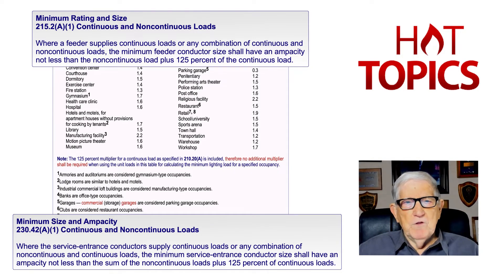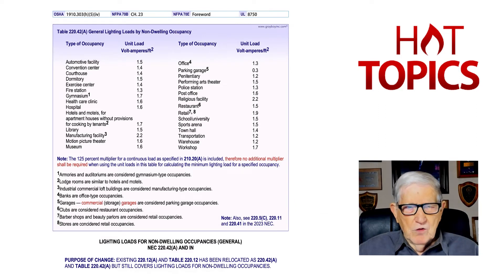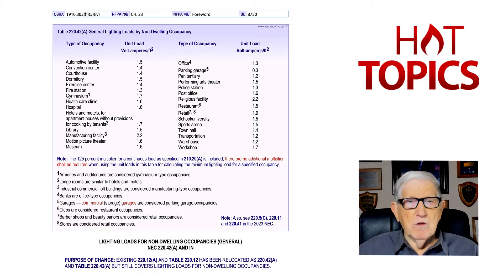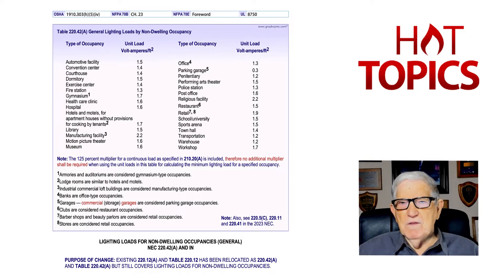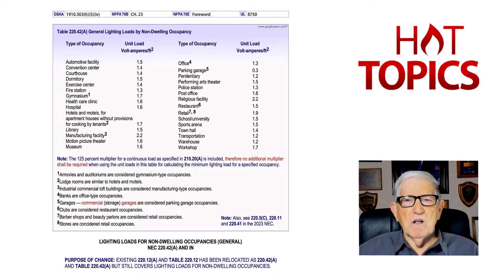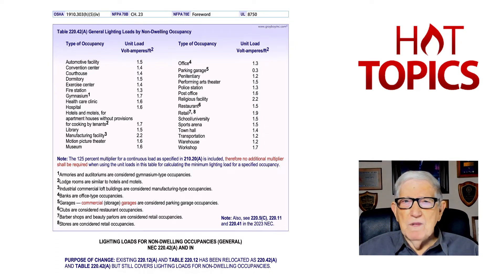If you take a look at a store building and drop down to number eight below the table — that used to be H, now it's eight — stores are considered retail occupancies. You would go over to retail occupancies, and notice that's 1.9 VA per square foot, which used to be three. They've reduced these VA ratings tremendously.